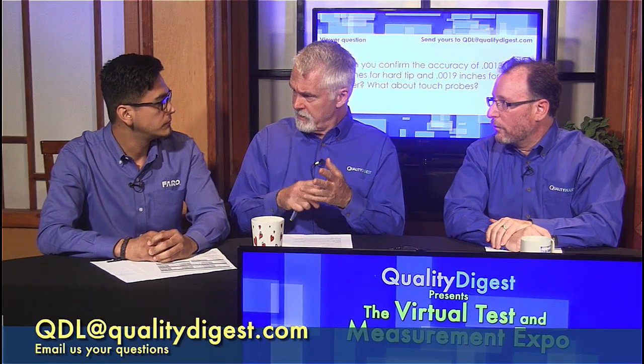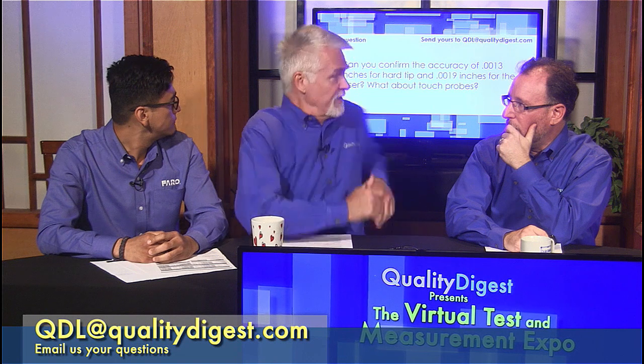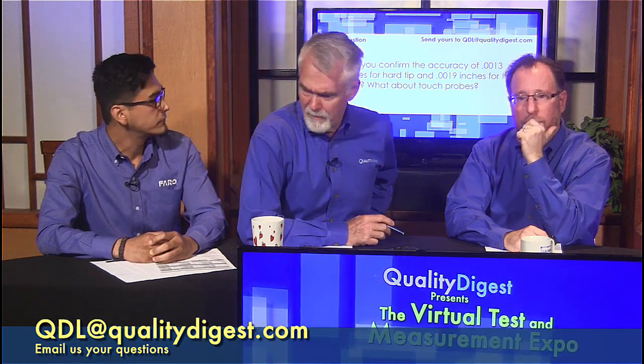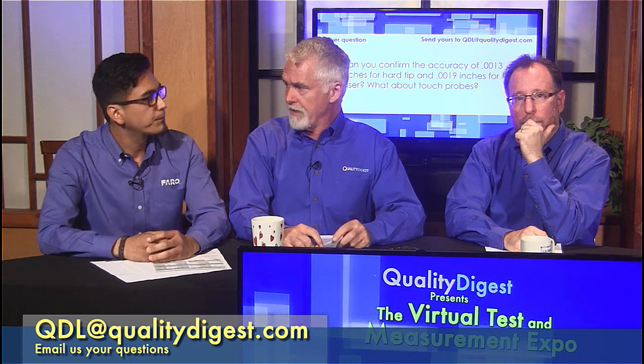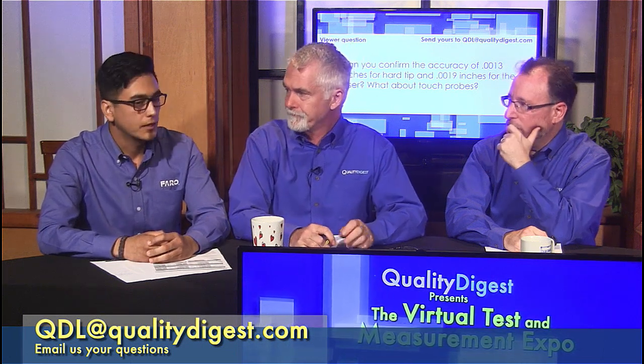So touch probes. You said in the video your accuracy was 1.3 thousandths for the touch probe and 1.9 for the laser scanner, right? Right. I think they're just asking how you confirm that, which is through your calibration. The calibration is NIST traceable. And to speak to the calibration of the laser specifically, to get that number, we measure a sphere of a known size at 5 different articulation points, and that's how we come up with that number. And these numbers are worst case scenario. With proper technique, you'll see even better accuracy results in your real process inspection.